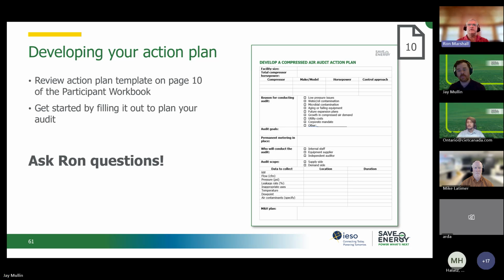Yeah, well, pressure monitoring meters are kind of a dime a dozen, right? But it's important if you want to do permanent monitoring of your system to purchase a fairly high quality, accurate meter. It could output maybe 4 to 20 milliamps or some sort of digital signal, right? And then have a data collection system. Very often large plants already have some sort of system where they're measuring their process variables, right? And feed that pressure into that system, come up with a dashboard, right? So you can see what the pressure is doing over time, right? And keep monitoring that to see if you're having a pressure problem when it's happening, right? And you might want to add instrumentation like maybe kilowatt meters to your air compressors, right? Flow meter, right? Could be analog or digital, feeding into the same system, right?